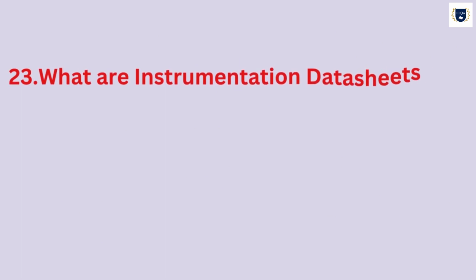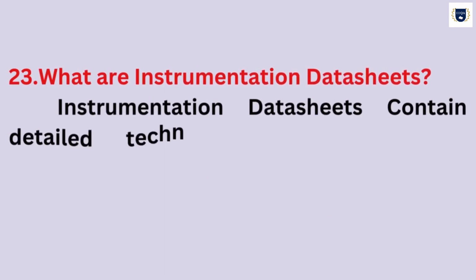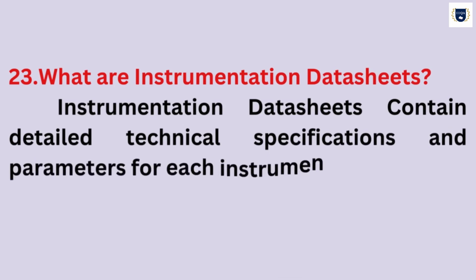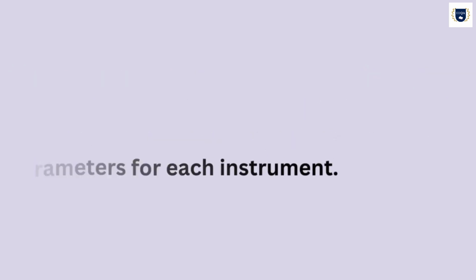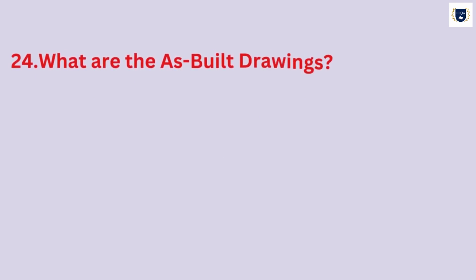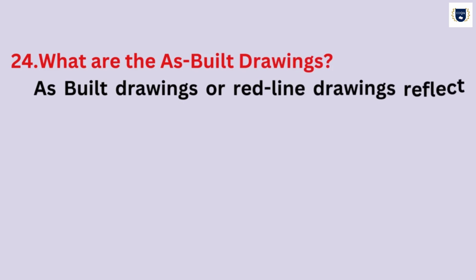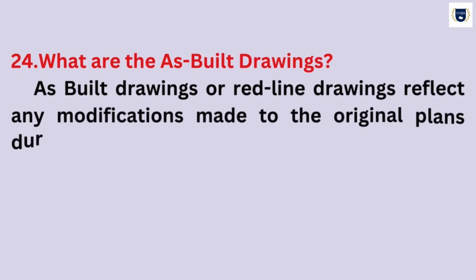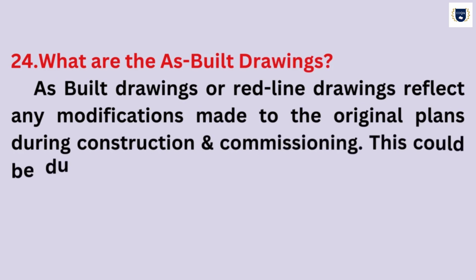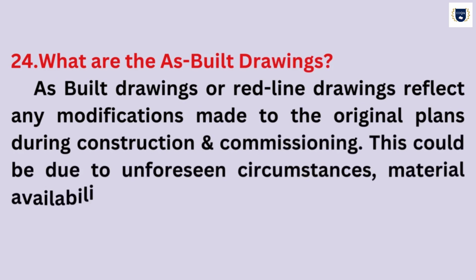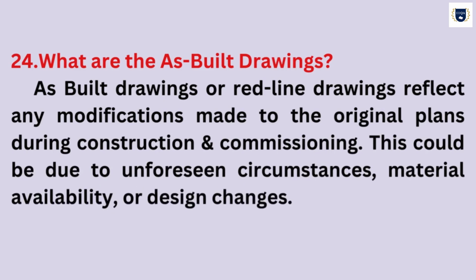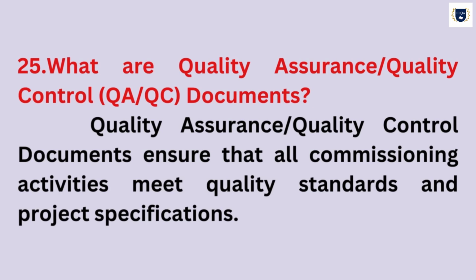What are instrumentation datasheets? Instrumentation datasheets contain detailed technical specifications and parameters for each instrument. What are the as-built drawings? As-built drawings or red line drawings reflect any modifications made to the original plans during construction and commissioning. This could be due to unforeseen circumstances, material availability, or design changes. What are quality assurance quality control (QA/QC) documents? Quality assurance quality control documents ensure that all commissioning activities meet quality standards and project specifications.